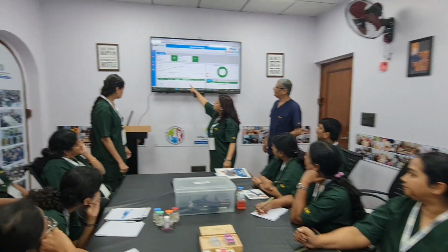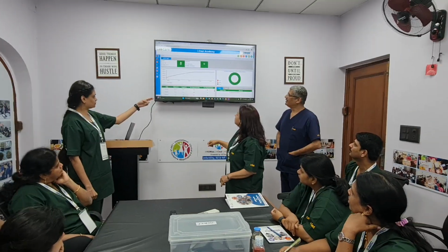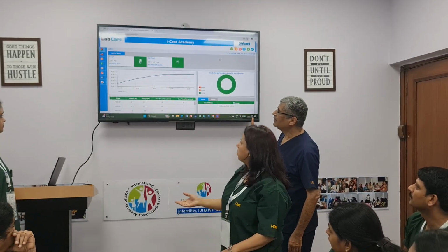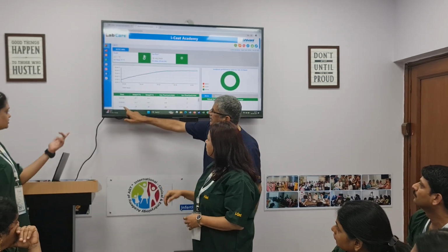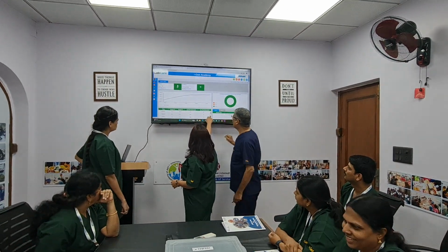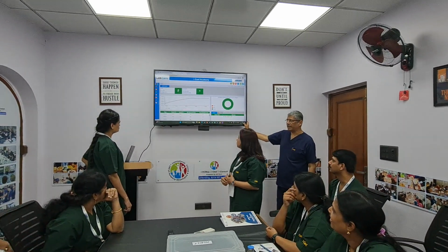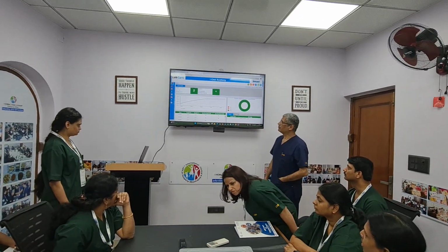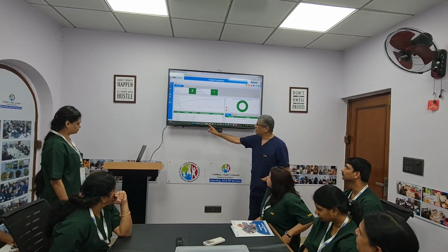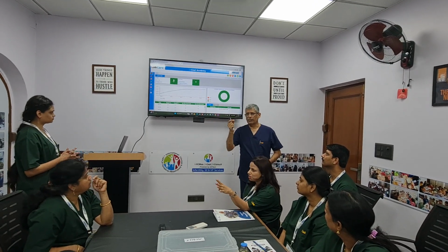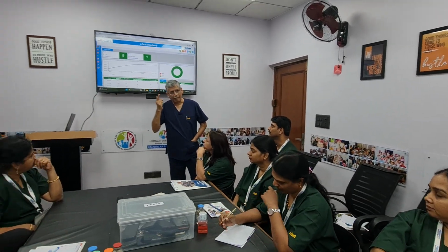Yes. So it has changed now to the normal gas flow. No, this is 10:27, you see the time. You opened it at 10:26, and now you are at 10:27. So that's the way it is: when you opened it, it was around 10:26, and now it is equilibrated. And you will find that the ideal set flow is 18 to 19 ml per minute.